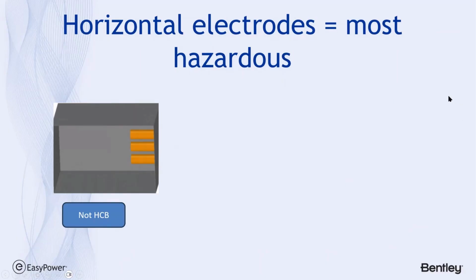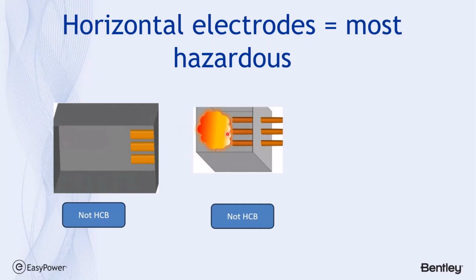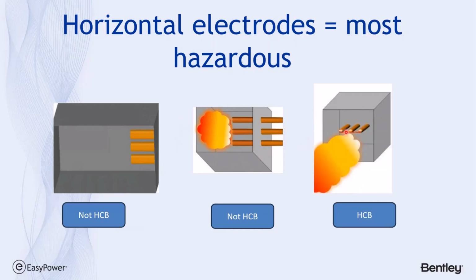And the most conservative or worst case hazard is horizontal in a closed box. Part of the problem is people are unclear as to the definition of horizontal in a closed box. For instance, these buses here are horizontal, but this is not considered to be horizontal in a closed box because the butt end of the bus work is within the enclosure. This is not terminating in a barrier, so it doesn't constitute horizontal in a closed box. What if I have the buttwork of the buses sticking out of the enclosure? In this case, this would be the most hazardous and the most conservative, but it's not necessarily what you encounter as far as your definition for horizontal in a closed box.